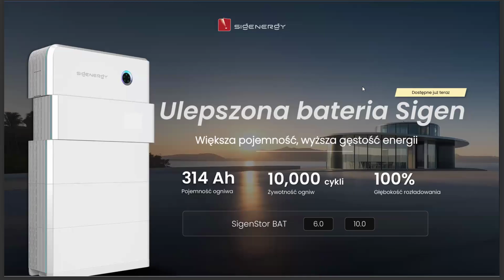Voltage management advantage, installer benefit. There is also an important technical advantage here. Thanks to the high voltage architecture and intelligent management within each module, our batteries remain stable across the full discharge range. We do not see sudden performance drops when the battery approaches a low state of charge. That means stable power delivery for the customer, and fewer service issues for the installer.